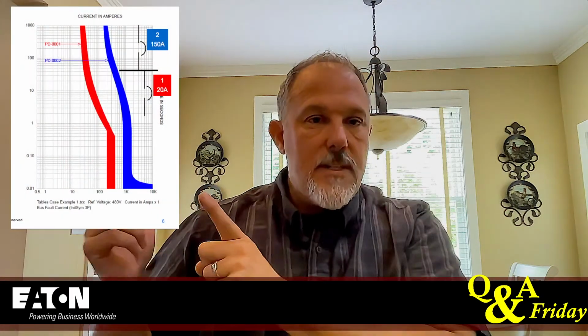Will both of those probably trip on ground fault currents, the most common fault in the power distribution system? Heck yeah. Will they trip on a bolted short circuit current? Absolutely they will. The only thing they won't trip on is an overload. Now, what you do for 0.01 seconds, you have to plot the trip curves, and you've got to just basically hide everything below 0.1 seconds. You don't even want to look at it because it'll make you sick if you know what you're doing. You hide everything below there. This curve right here, 0.1 seconds, works fine.